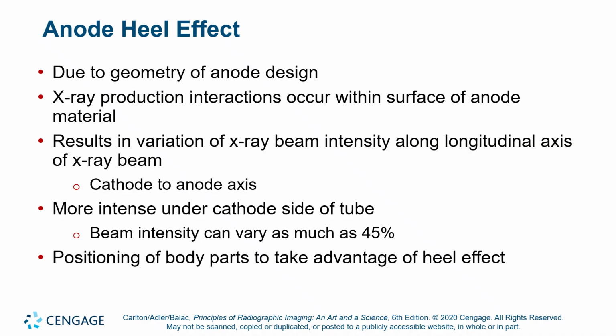And that's the bottom posterior corner of the target anode. And so those X-ray photons traveling through the heel encounter molybdenum and graphite, which is carbon. There is some photoelectric effect going on, especially in the molybdenum. And so immediately part of the X-ray beam we generate at the focal spot is reabsorbed by photoelectric effect before it ever has a chance to leave the X-ray tube. It's reabsorbed by the anode heel. So what happens is there are fewer photons per square centimeter on the anode side of the beam than there are on the cathode side of the beam.